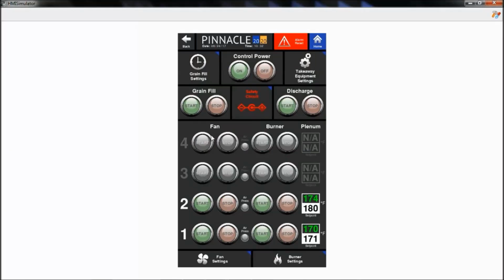So, couple notes here. Anytime that a critical alarm happens, we assume that a person is in danger. So that includes high limit alarms, that includes e-stops, anything that's part of the human safety circuit. For those alarms, everything cuts power immediately. So your grain fill and discharge will stop right away. Any applicable timers will not run, and fan and burners stop immediately. So this is the least graceful shutdown of the dryer, but it's deemed to be an emergency, so we essentially pull the plug and turn everything off.